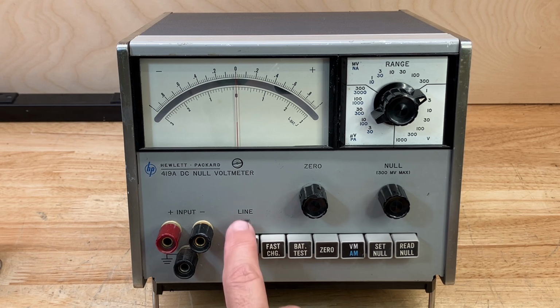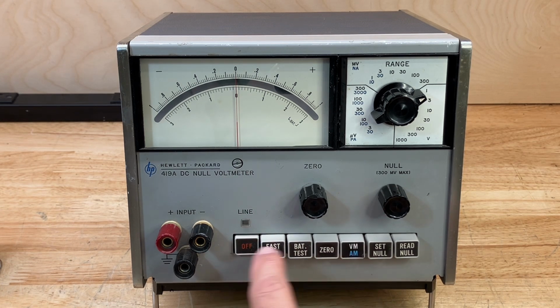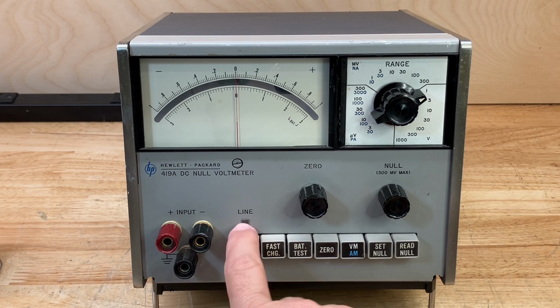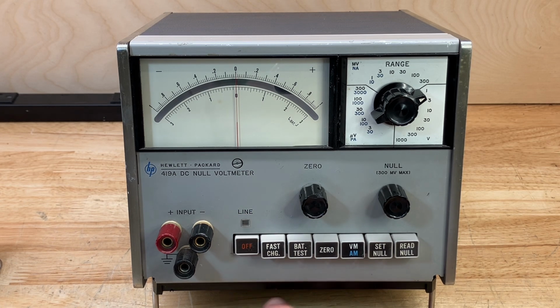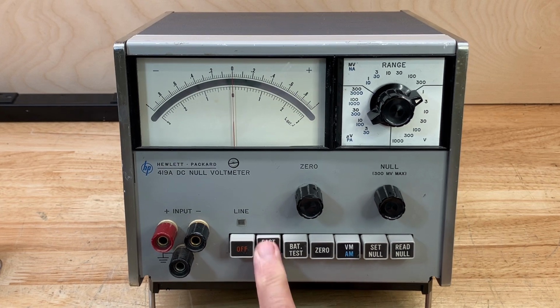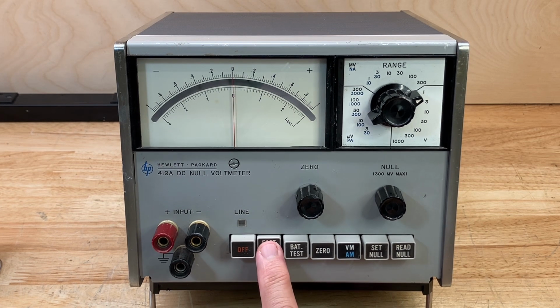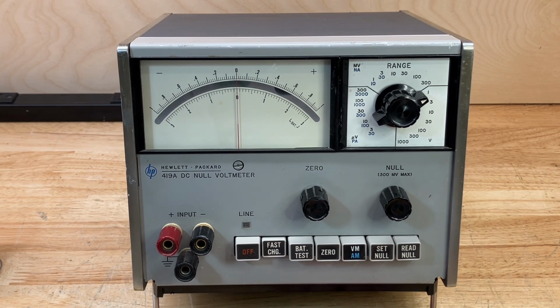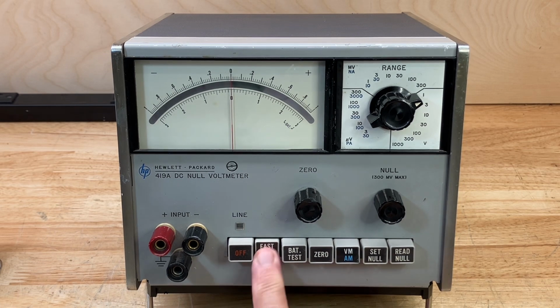Off — there's a line indicator. When you select any of the other push buttons, the off button pops out and the line indicator turns on whenever it's plugged in. When you select fast charge, it charges the battery at a more rapid rate. The instrument can't really be used when it's in fast charge mode.